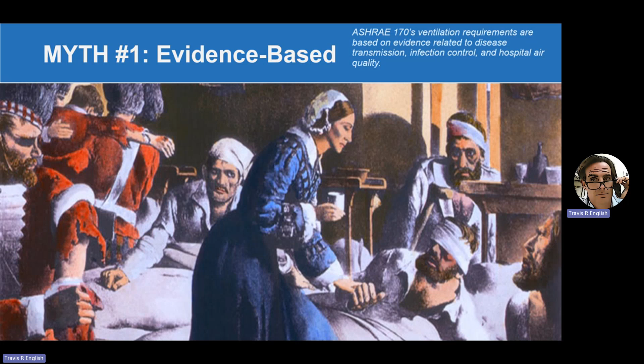You can go all the way back through 150 years of literature, and you will not find a single author since the Victorian era who positively justifies 2 air changes per hour. Like, 2 air changes per hour is the right number, and here's why. Nobody's said that since before Sherlock Holmes. The other rates like 4 air changes per hour and 6 air changes per hour and 10 air changes per hour usually come from the 1950s and the 1960s, and we've been repeating them ever since that era.